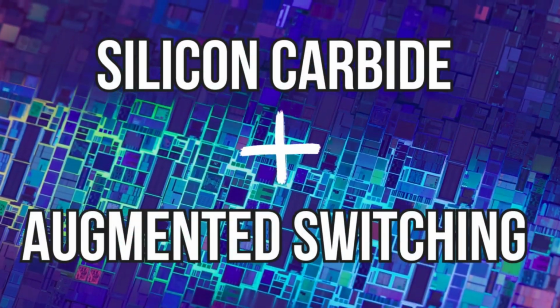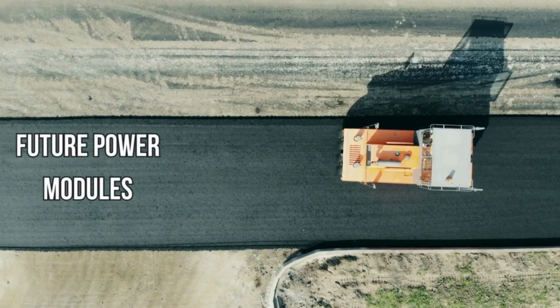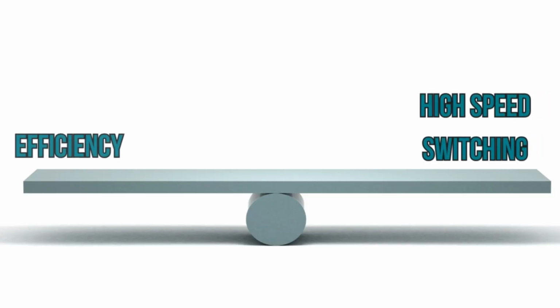And the same thing at turn-off. You have these intermediate steps that are configurable, and that really helps with the switching performance. So the dV/dt and the dI/dt overshoot will be minimized, with less ringing, and you can have better EMI performance. Silicon carbide and augmented switching are paving the way for future power modules, balancing efficiency with the intricacies of high-speed switching.